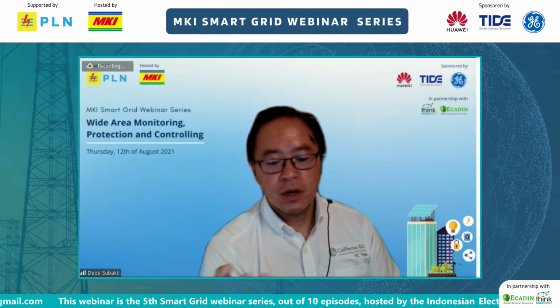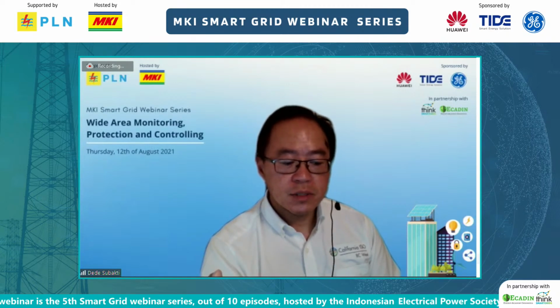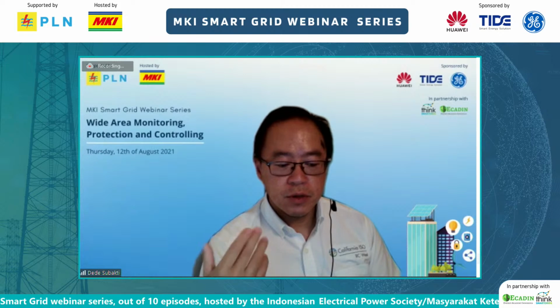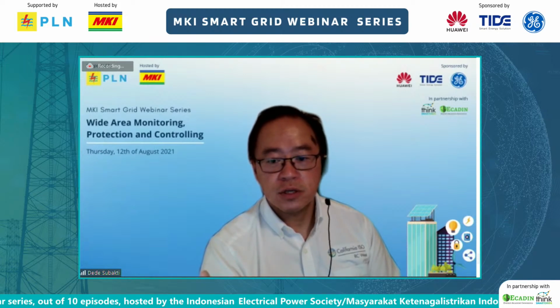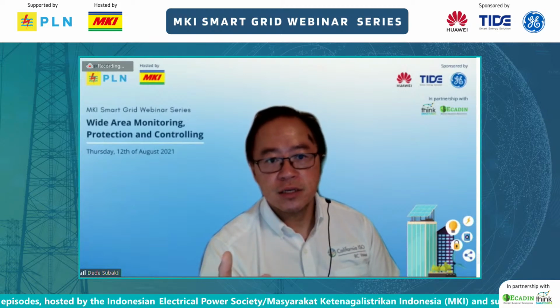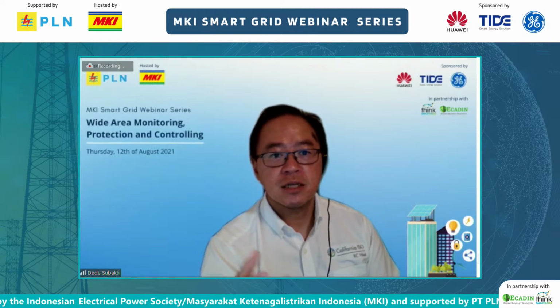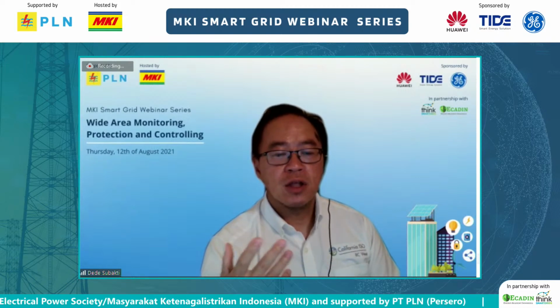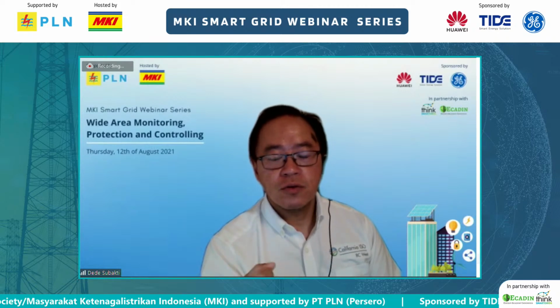But before people go there, there are actually other items, such as putting in synchronous condensers. We have a lot of synchronous condensers. The synchronous condensers actually put mass in the system. It also has voltage control. It has a lot of other items you could do there. So synchronous condensers, SVCs, those are the cheaper options. If they're not online, put them online. But the more expensive option is when you start redispatching generation out of merit to reduce that power transfer.